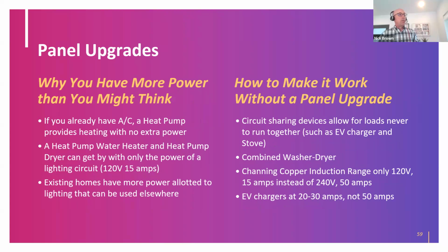You may have more power than you think, because if you already have air conditioning, that amount of power is enough to switch that to a heat pump. A heat pump water heater and a heat pump dryer can both be run on 120 volt, 15 amp circuits now. Some heat pump water heaters are 240 volt, 30 amps, but I put in the 120 volt, 15 amp from Rheem for my main house, and it's working great. So they're making systems with lower power requirements that still do the job.